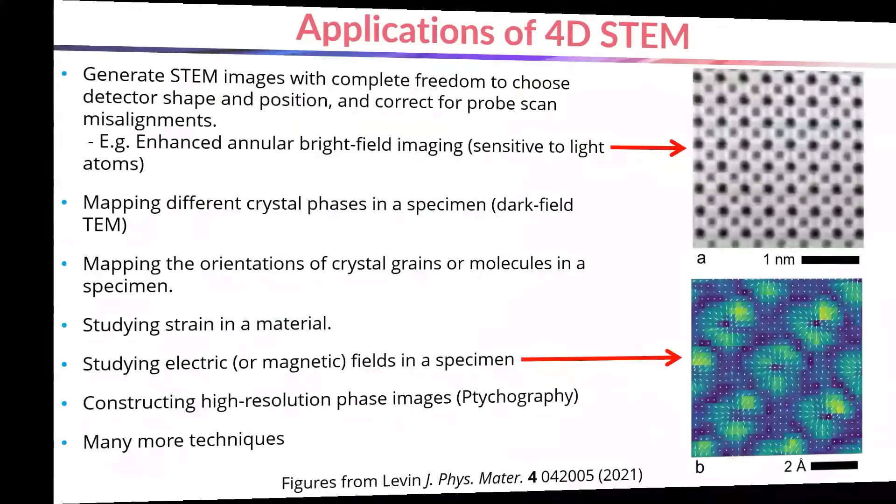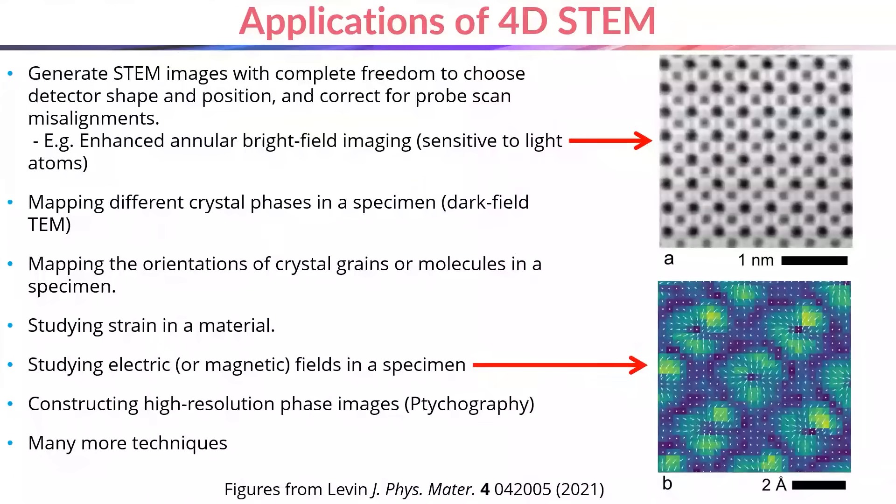So what are some of the applications of the technique? For one thing, you can generate 2D virtual STEM images from the 4D data by masking part of the diffraction patterns and then summing the information in them together. You have complete freedom in 4D STEM to choose the size, shape, and position of the mask you use so that you can maximize the signal that you're interested in.